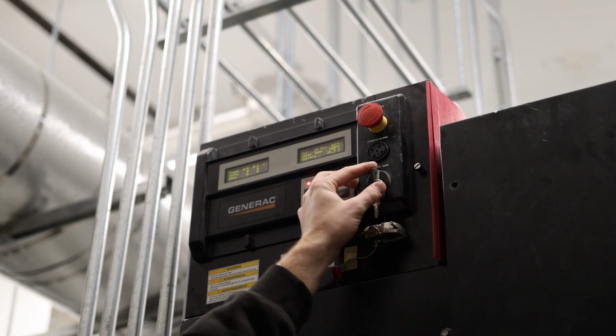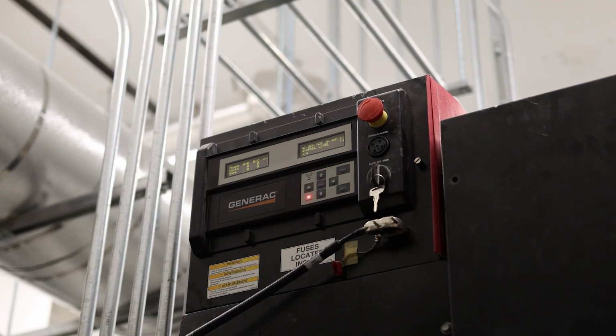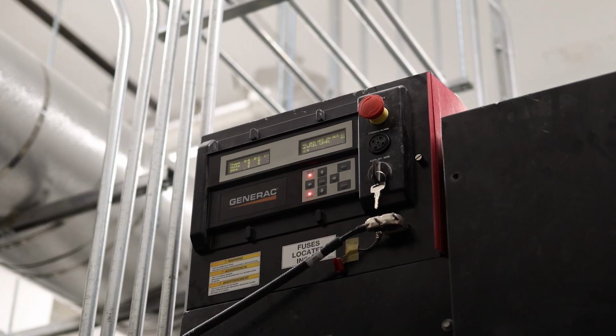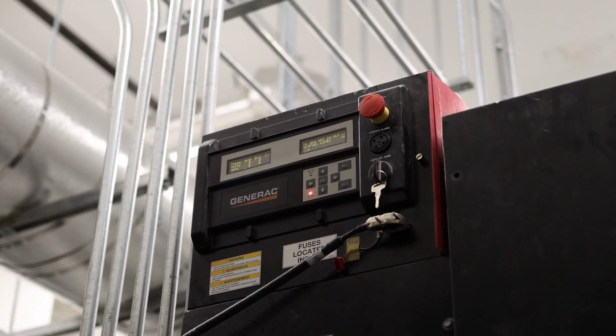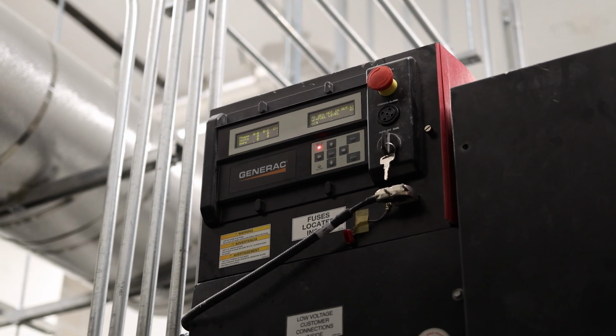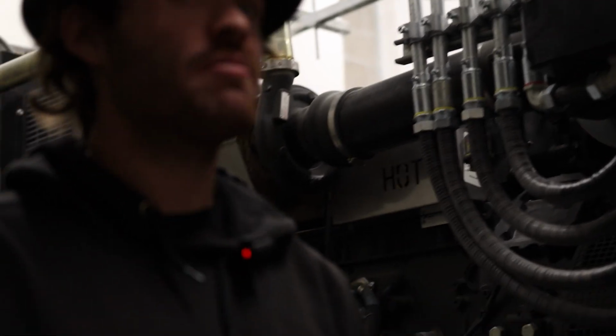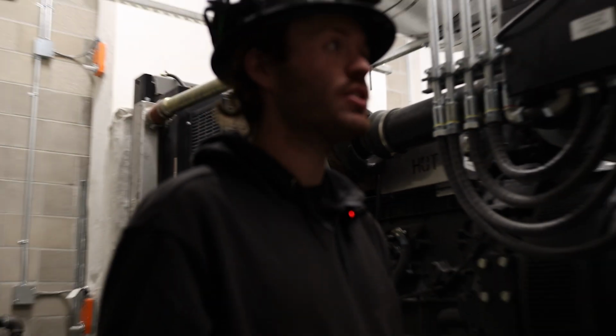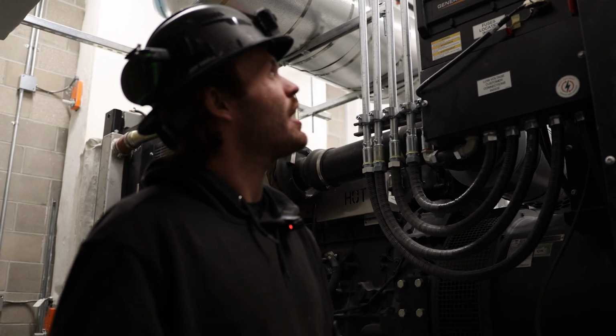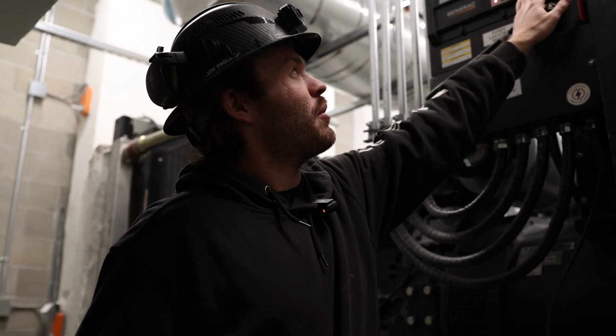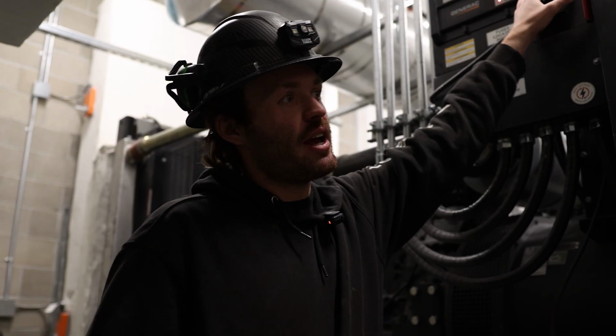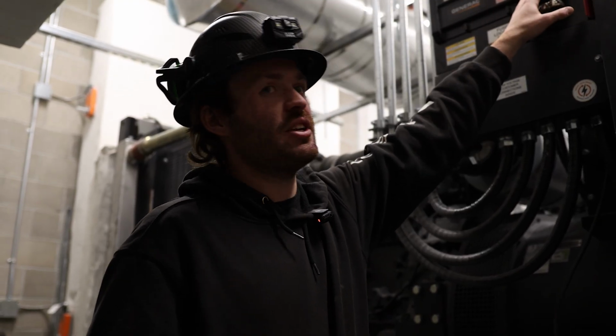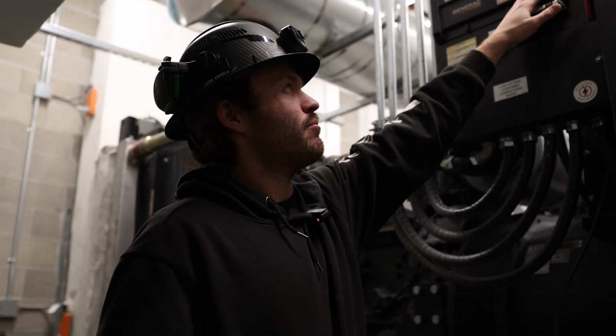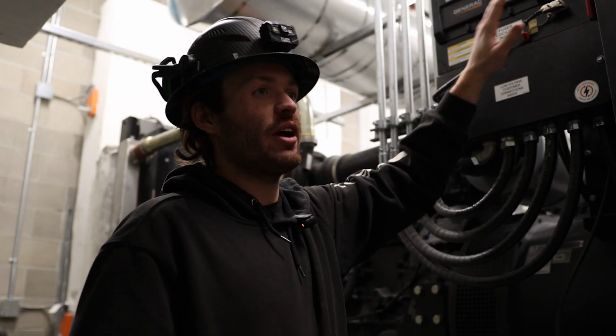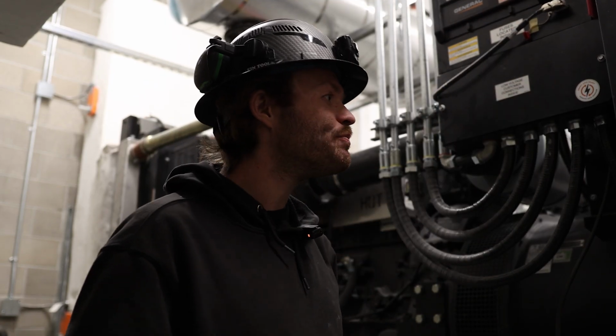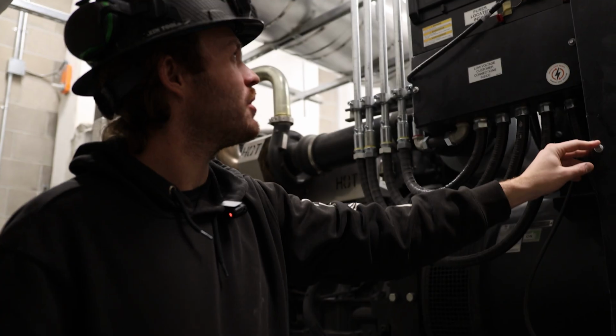Off is to do maintenance inspections, testing, anything of that nature. It's how you isolate the unit so you can service it, so you can get a better look at your belts and not get your hand chopped off if it automatically starts, any of that nastiness. And then if we go to the right one more, it will manually start the unit, and as long as the key is in that position, it will continue to run manually. Flipping it back to off will turn it off, or any shutdown alarm will also shut it off. We'll do that here in a moment.